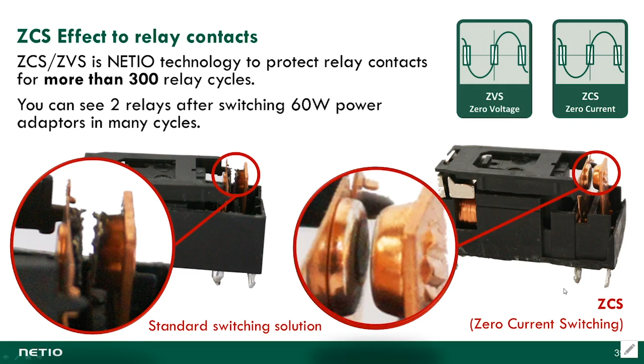So how is it happening? If you switch on more or less any electronics today, there is a peak of current within a couple of milliseconds, called inrush current, and this effect harms the relay. It doesn't harm it immediately, but after dozens or hundreds of cycles, depending on what's connected. If there's an LED light or a UPS, it can be as few as 300 or 400 cycles; with something different, it can be several thousand cycles. But we're still talking about 1,000 or 2,000 cycles, not 50,000.